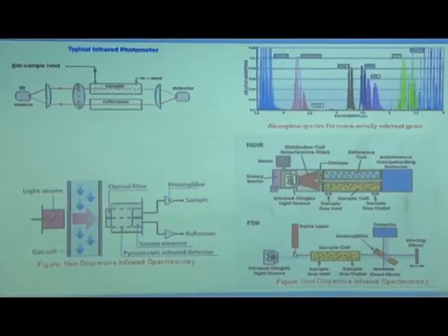This is absorbed by one side of the detector, the other is absorbed by the other side of the detector. So, on one side of the detector the pressure will increase, because there is more energy, and on this side, since some of the energy is already absorbed by the sampling gas, the energy will be less and the pressure will therefore be less.